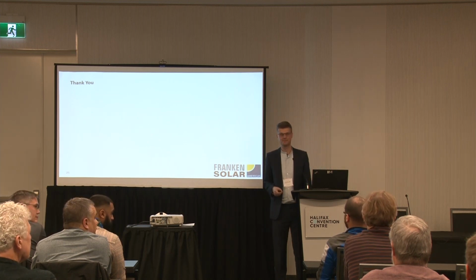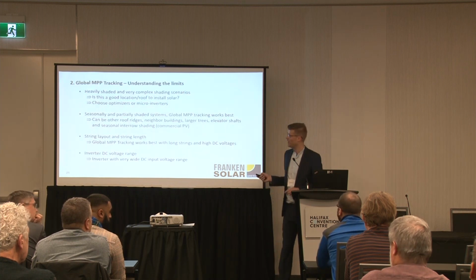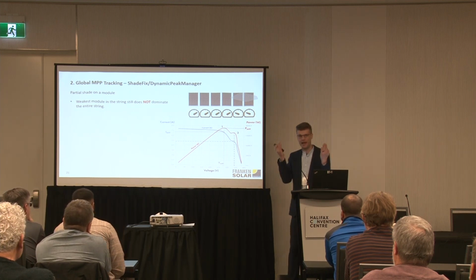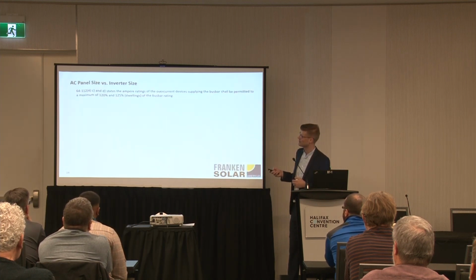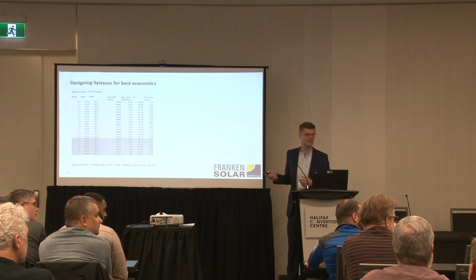Go ahead. Yeah. So when you were preparing your simulations for the clipping with your higher DC to AC ratios, how did you figure out how much is being clipped off with each? I actually even listed, so there's a so-called PR ratio, performance ratio, that puts the potential yield with the actual yield in perspective. Let me quickly go back. And there you can see actually what clipping losses you have. Just a heads up, it's probably the last question.